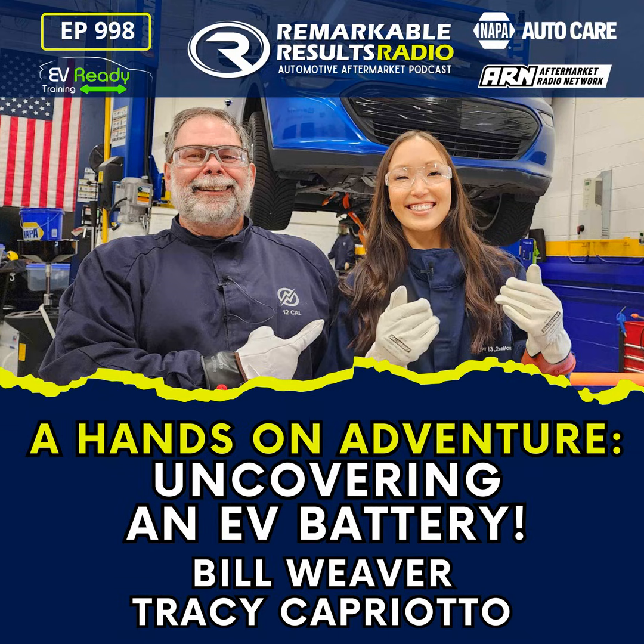The garments that we have on, whether we talk about Tracy's full length suit or my jacket and pants, both of these items have an arc thermal protection value. Mine's 12 calories, hers is 13.2 calories per square centimeter. This refers to the ability of that garment to protect you in case we have what they call an arc flash, a lightning bolt, a catastrophic failure of one of the conduits inside of here that could seriously damage us.